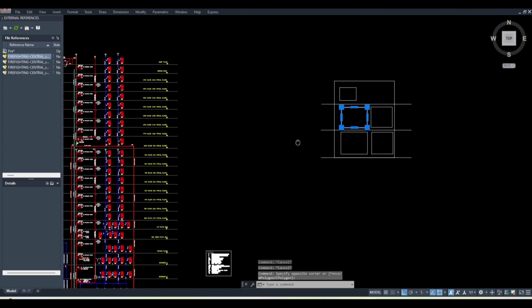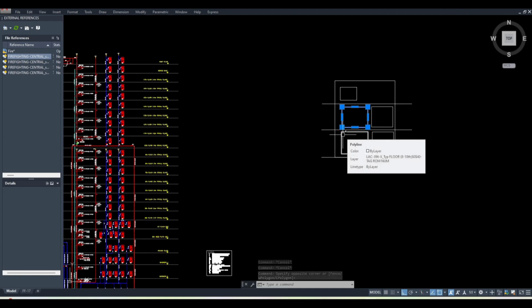In the ordinary hazard we are normally using one sprinkler to cover 12 meter square. So can someone tell me, in one fire zone how many maximum sprinklers can I install? Tell me, calculate it quickly. Anis, you no need to refer to the previous lectures. I'm just telling you completely today. So I told you one zone has to be 4,831 meter square, right? Let's say that is the area of that zone. Then one sprinkler can cover 12 meter square. So how many sprinklers can I install in one zone?